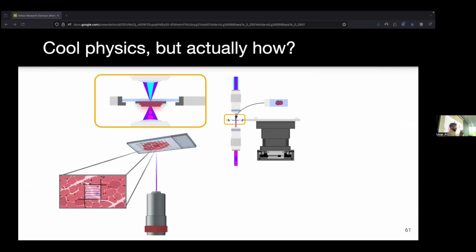This section is where the magic happens, where some of the cool contrast stuff comes out. Basically, you have the excitation path that goes up into the tissue and gets absorbed by the tissue. It'll heat up and start vibrating, and it'll fluoresce basically at the same time. There's a very small window in which you're capturing that. Because we're doing it in pulses, every pulse you'll see that event, and then it'll relax back down, ready for the next event. That's why it has to be in pulses.